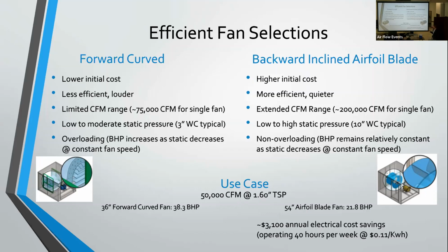Compare that to a 54-inch airfoil blade fan. You're running it at 21.8 brake horsepower. So 38.3 versus 21.8. If you run the units 40 hours per week, that equates to $3,100 annual cost savings, or electrical savings, just by using a more efficient fan. Mark, I think you should probably recognize this because I think I laid this out for you a couple weeks ago. So actually the payback for that, I think, was about a year or so.